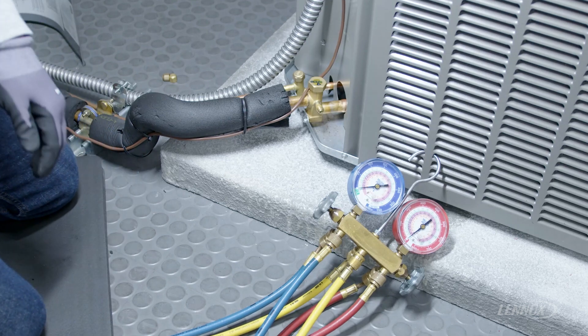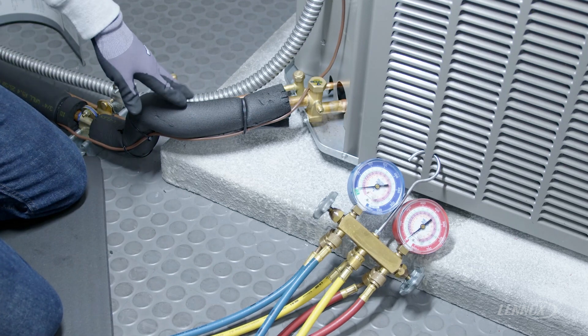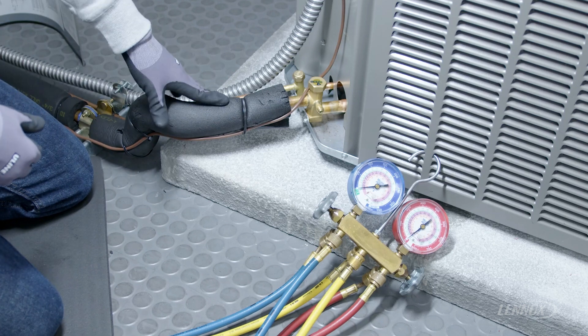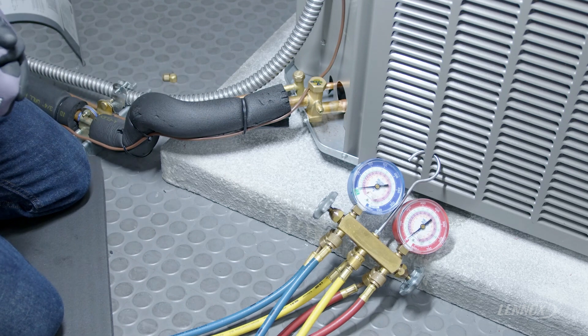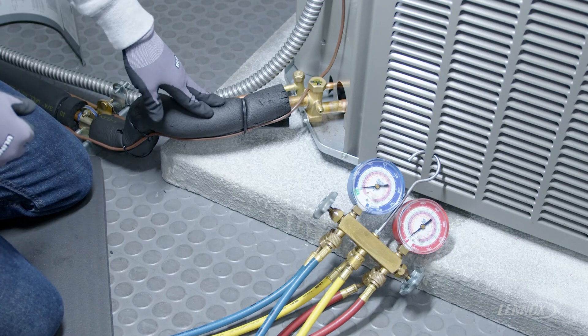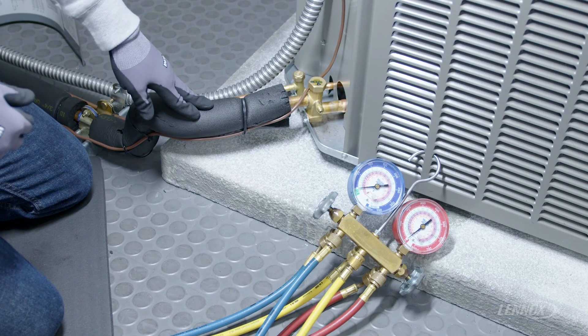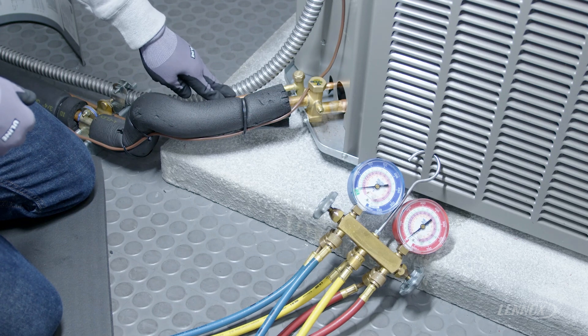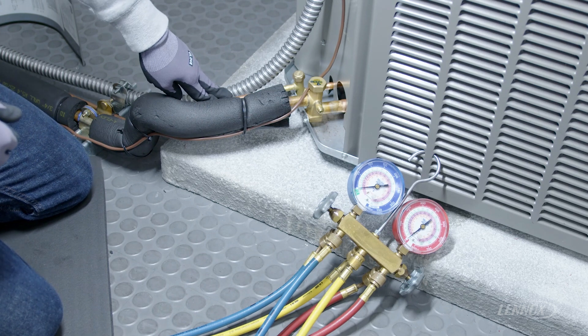Once you've removed your caps, you then need to identify which line you're going to hook which hose of your refrigerant gauge set up to. There are two lines on every air conditioning system, a larger line that we call the suction line or low side of the system and a smaller line that we call the high side or liquid side of the system.